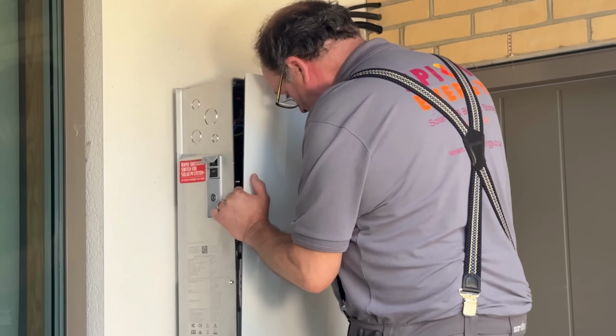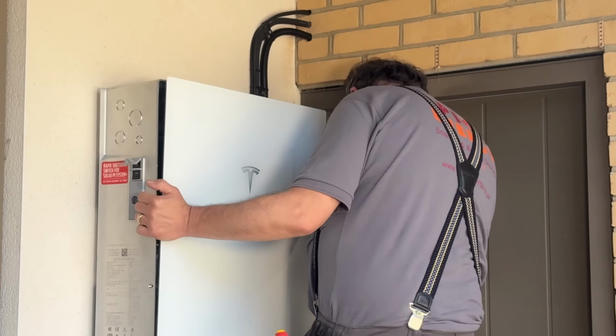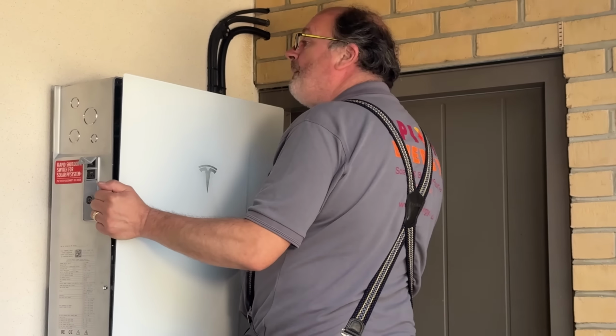Tesla also advised that the main Powerwall 3 is allowed 30 centimeters of free space in front of it for airflow and cooling purposes. So that's also something to consider if you're going to squeeze a battery pack behind it. If you do stack the batteries, then you obviously won't need to pay for the frosted glass pane that you'd buy if it was going to be mounted adjacent on the wall.